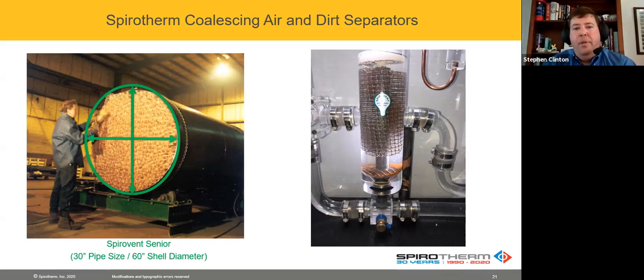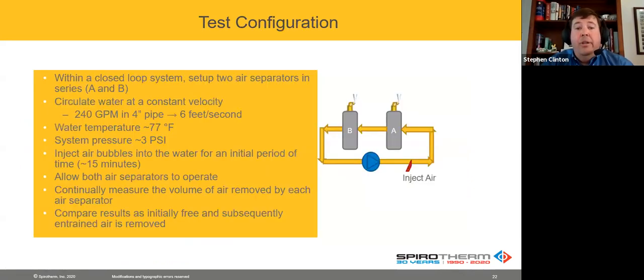It's those very small bubbles that over time collect others and are removed. Now, people ask us, how do you hold up against a regular separator? I've been specifying those for decades. Why should I change? What we did was we mocked up a system and we said, let's put one unit in series with the other, put a traditional air separator in line with ours, run it for a period of time, measure the amount of air being removed, swap it, do it again. Let us be first and let them be second.